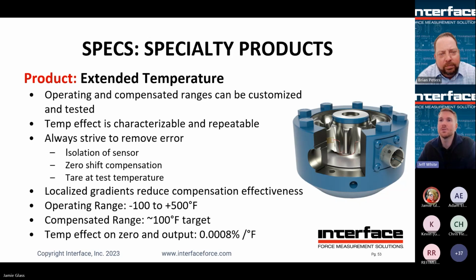So, extended temperature. First, we need to understand how these are affected, but also how we compensate. Temperature is often repeatable and very easy to characterize. So we are able to remove the error and isolate the temperature. One thing that would be good is just to isolate the cell from the temperature if possible. And of course, we are going to compensate the zero balance and span up to a certain capacity if requested.